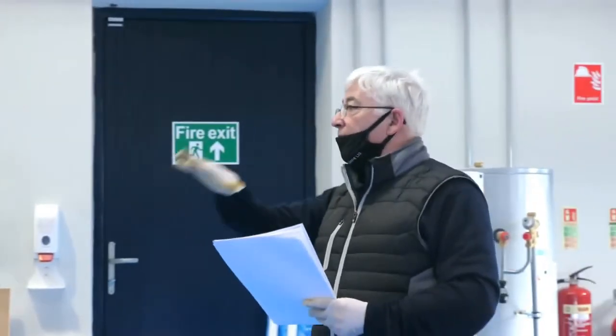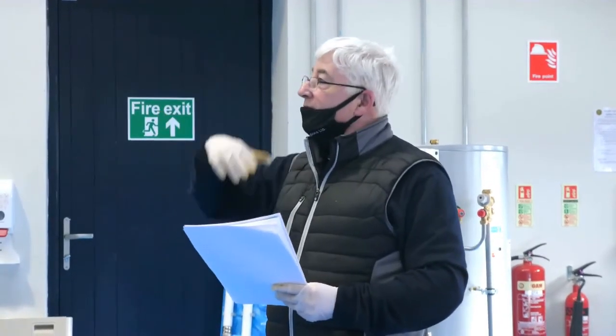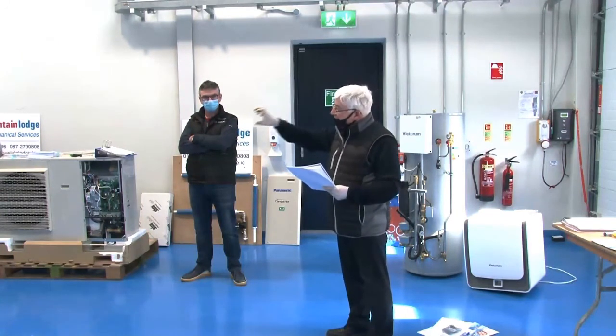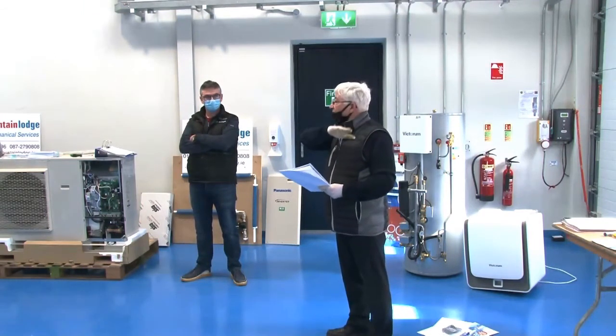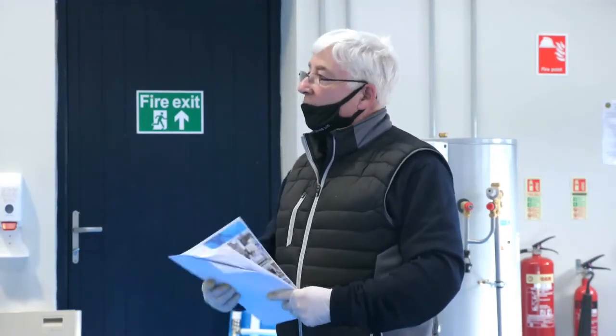On a heating system, your heating system will generally operate at 1 bar with a 3 bar lift off. So we're looking for 3 bar and 95 degrees maximum temperature, say, which you're never going to get close to with a heat pump anyway. Your service conditions with a heat pump would be 3 bar and 55 degrees. So if you have a pipe that's 6 bar and 95 degrees, you're safe. That's not a problem.